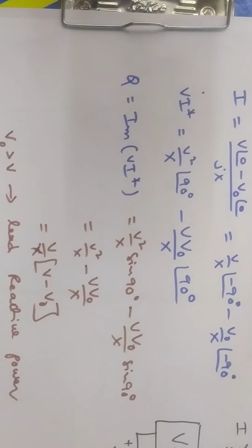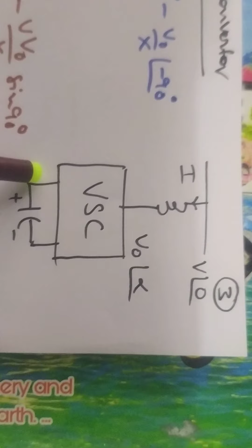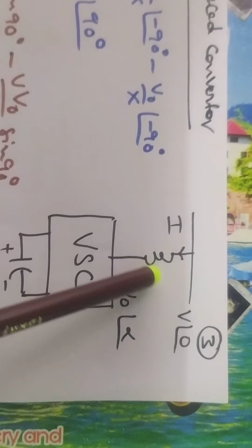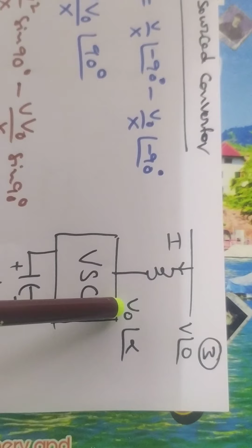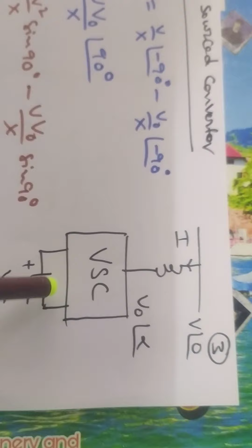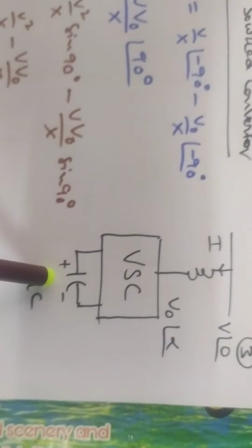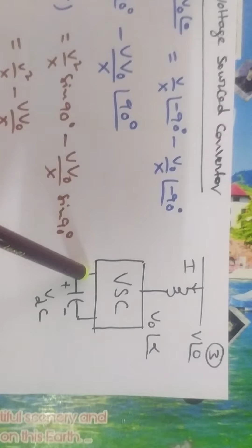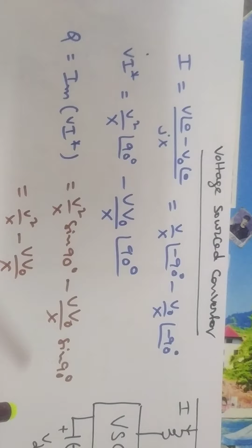Coming to the voltage source converter, this is the voltage source converter. It is similar to your synchronous condenser. This is the coupling transformer, leakage reactance, bus voltage V at 0, internal voltage V0, the output voltage of the VSC at an angle alpha. So this is the DC voltage VDC across the DC capacitor. The current is the current flowing through the VSC. So it is capable of supplying both lagging as well as leading reactive power.